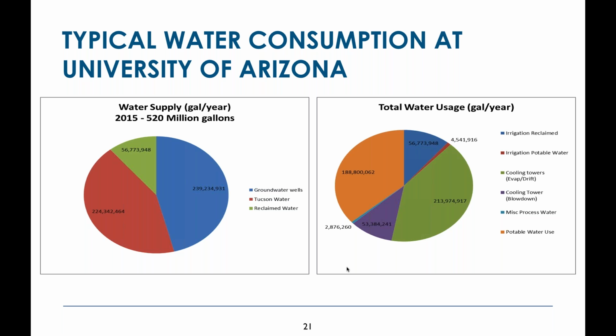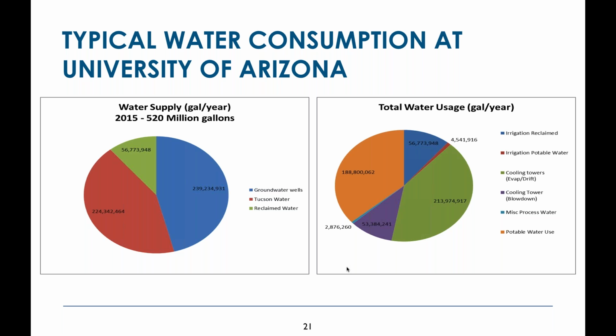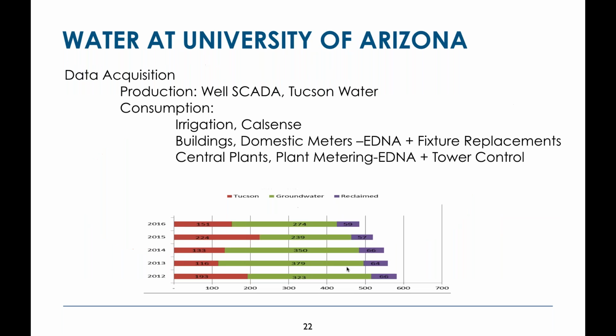If you look at the graph on the right, you get a sense of how that water is distributed. I want to bring your attention to the green and the purple, green being annual evaporation in the cooling towers, purple being annual blowdown. We'll talk more about that, but together they make up over 50% of the total water used on campus each year.